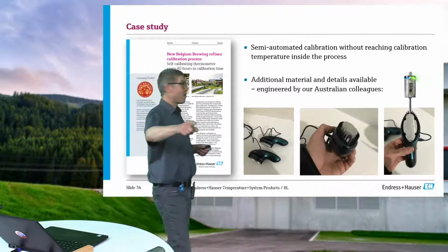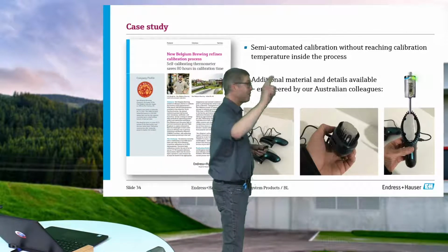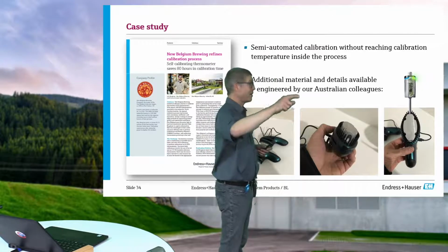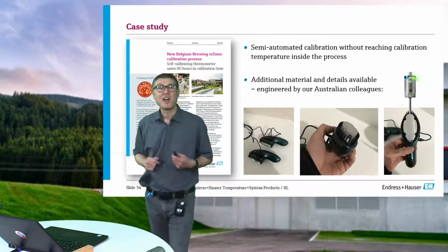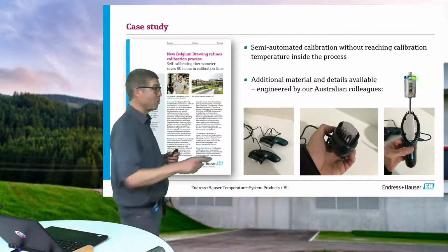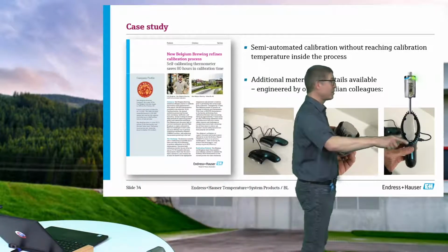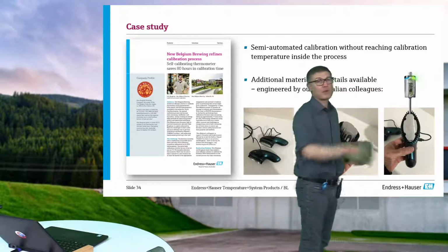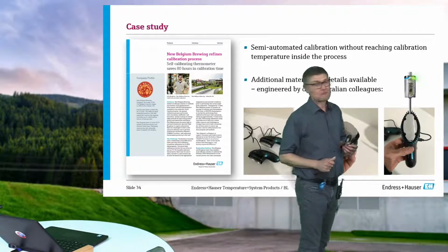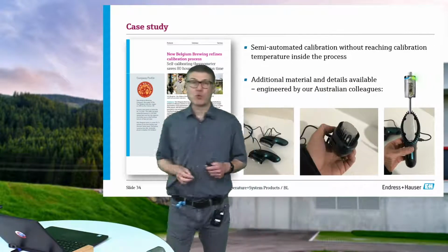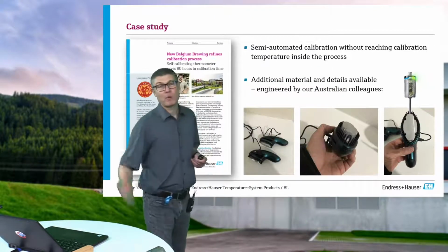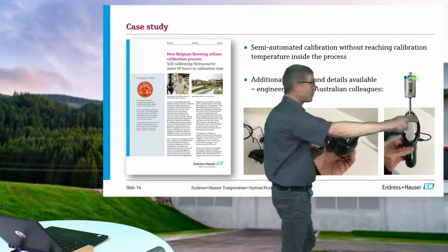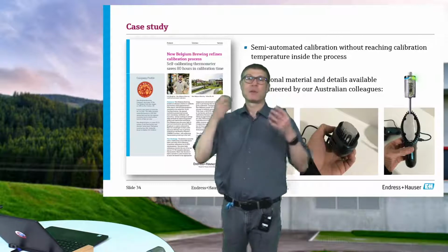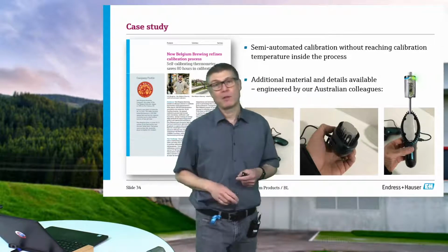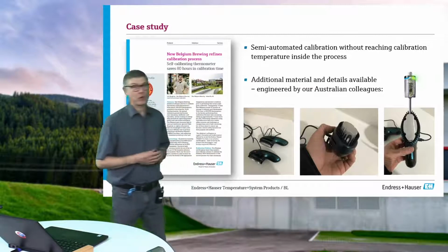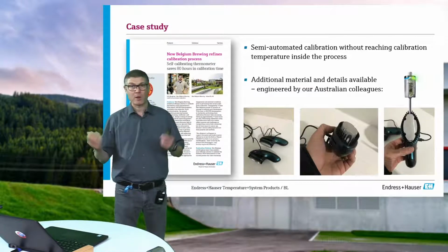And also, our colleagues in Australia have invented a mobile battery-powered calibration device for the Trustsens, which is working in a similar principle. You put your sensor in it, you heat it up, you let it cool down, you have your calibration, that's it. And if you like, you can go to your plant with this battery-powered hair straightener and a box of ice cubes, and then you can have your second point in the calibration. If you have already taken your sensor out of your application, why not?